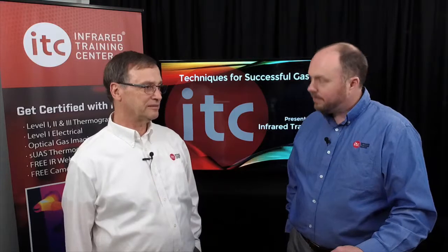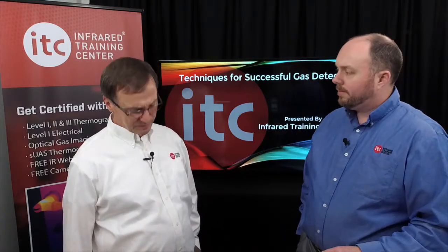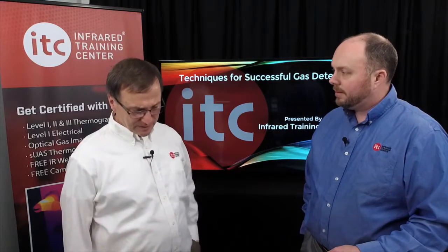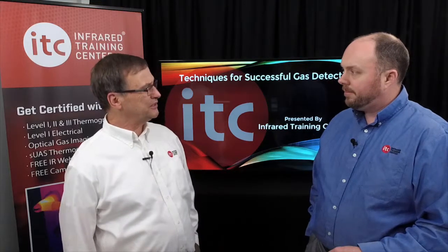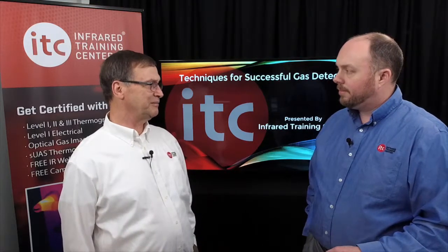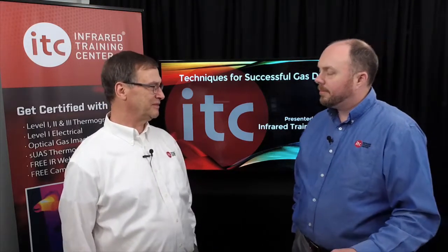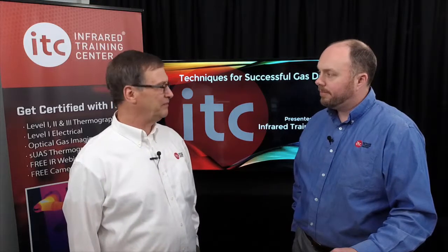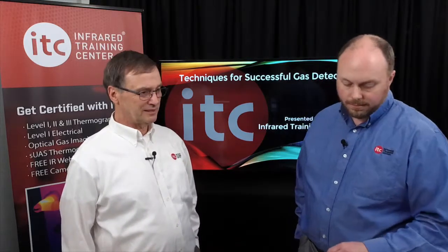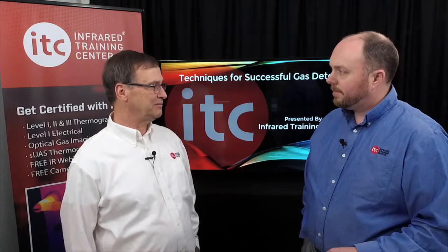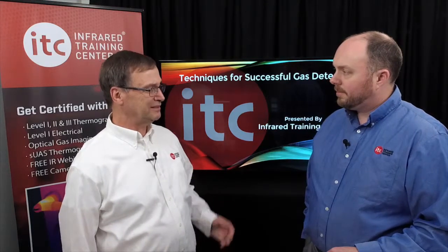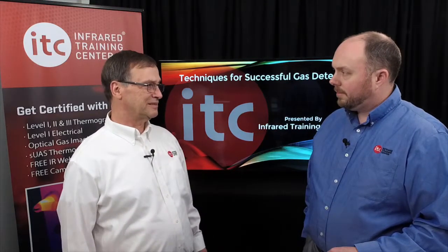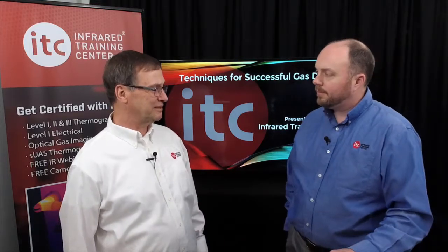The only requirement that I know from EPA is they wanted folks to look at, I believe it was, not sure if it's in the regulation anymore, it was transmission storage tanks. They wanted a 5-minute observation time, and you do not need a 5-minute observation time with these cameras. If you sat back and you looked at a flange or a valve stem or something, and if you don't see a leak within, I'd say 15 to 20 seconds, there probably isn't a leak there.